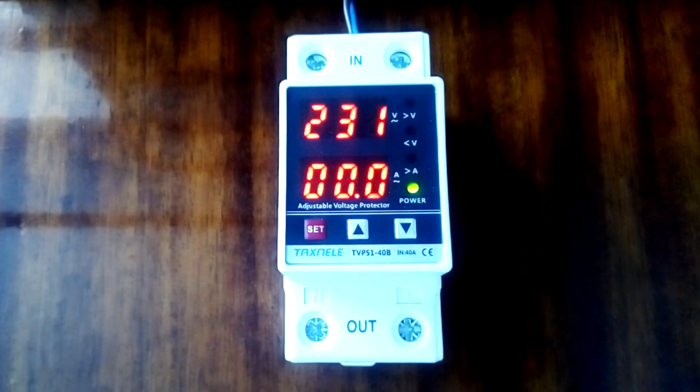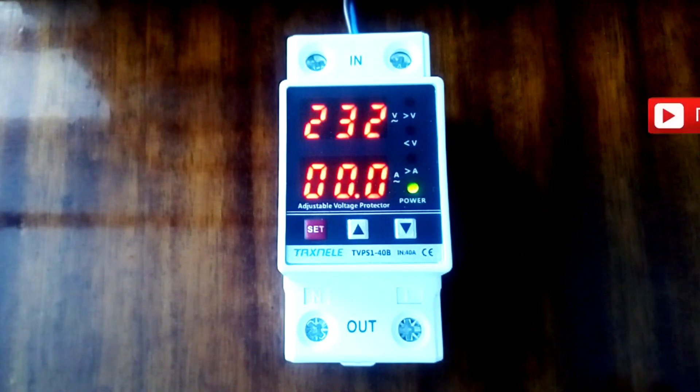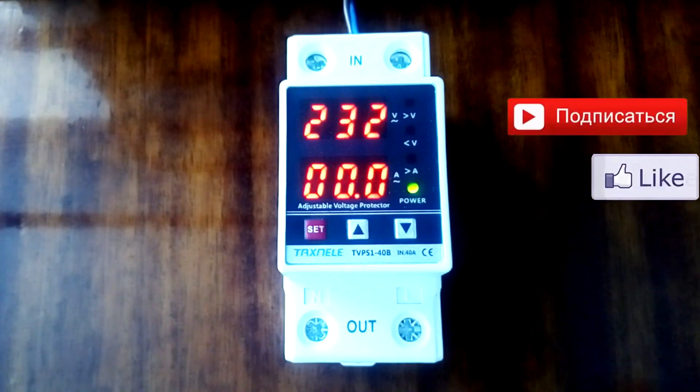The relay is already set to default relay trip values. For example, the upper threshold is 270 volts and the lower threshold is 170 volts. I do not agree with these values, as well as with the standard relay response time. I will record and post another video on the channel where I will show what relay settings I made for myself. I will post the link in the description. Subscribe to the channel and press the bell so you don't miss this video.